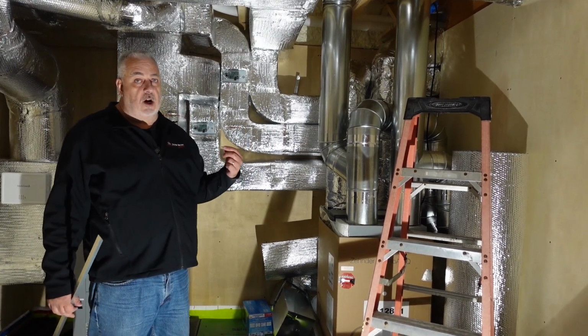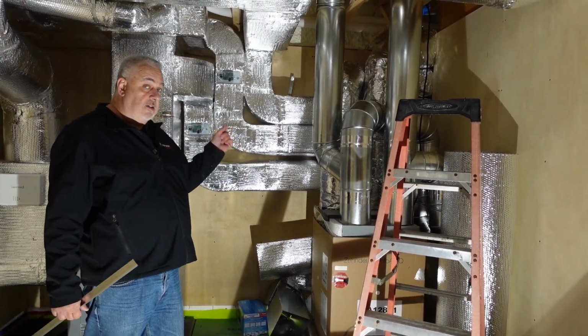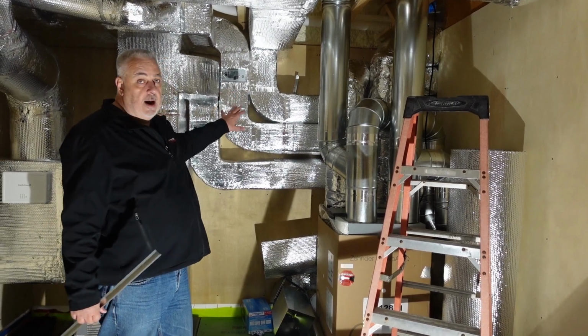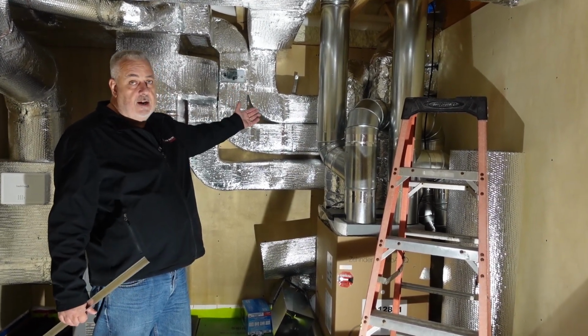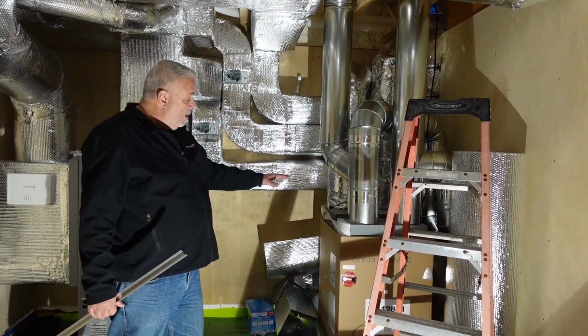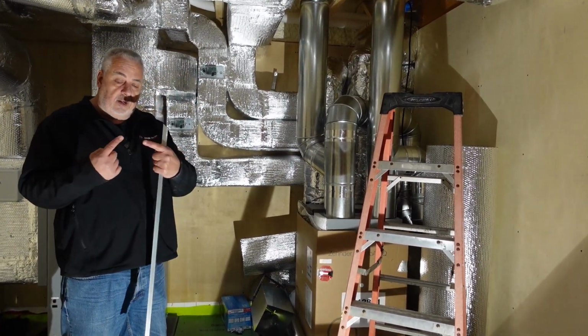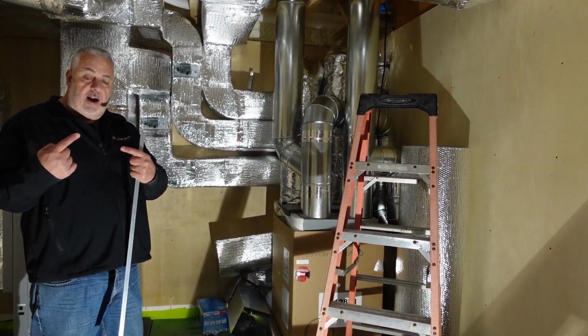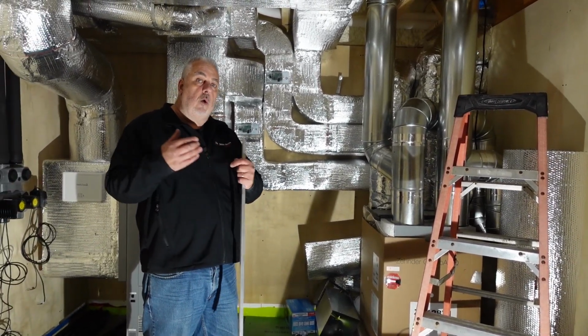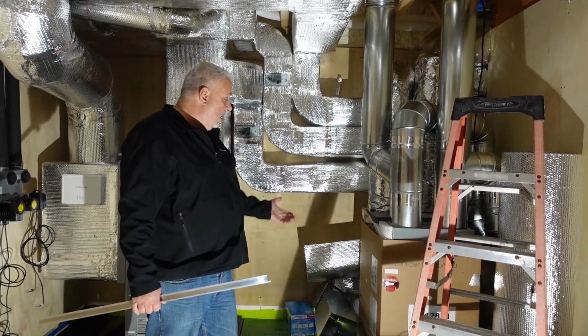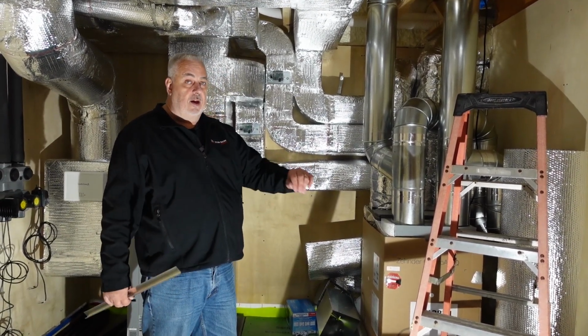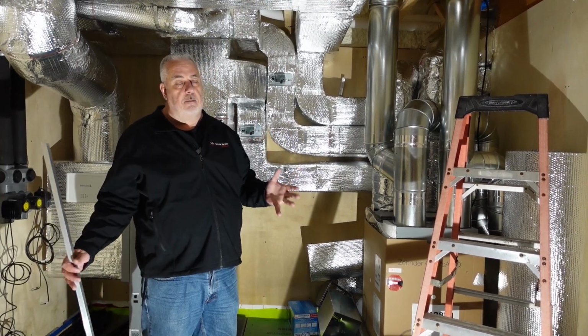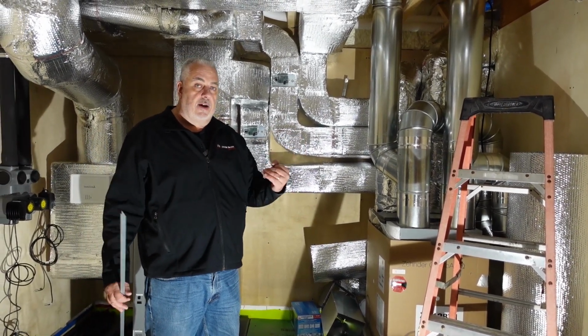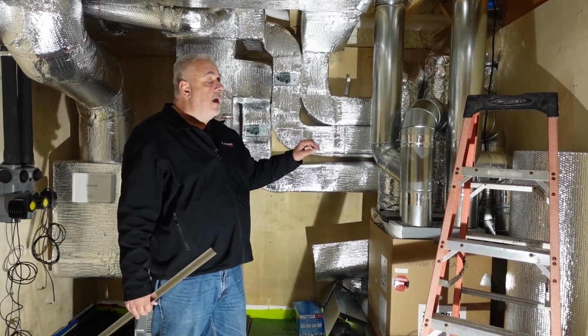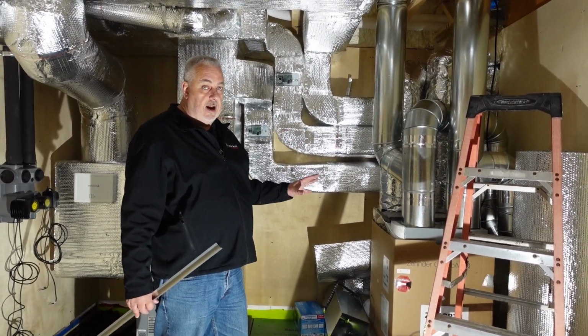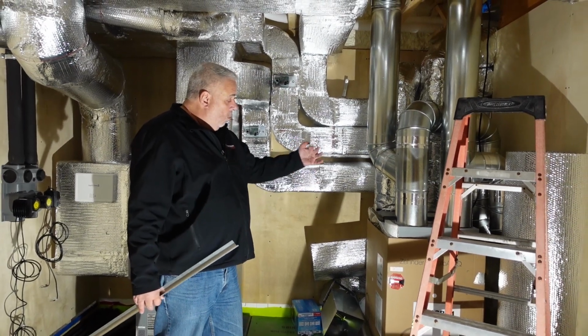There's a supply and exhaust to the house, and a supply and exhaust to the outside. So as it brings the outside air in, it runs across an enthalpy wheel, and the exhausting air from inside the house that's collected moves across that wheel and strips the energy off of it. That's why it's called an ERV, Energy Recovery Ventilator, because it conserves the energy that's bought and paid for in the house and extracts it off the exhausting air to the outside and puts it on the air coming inside.